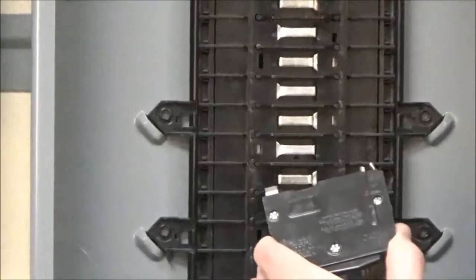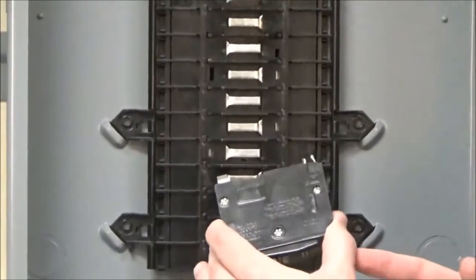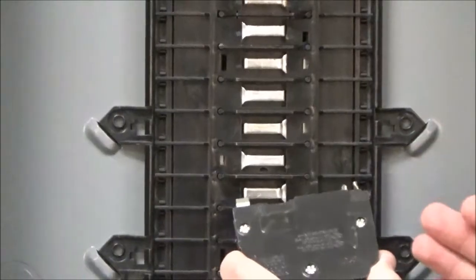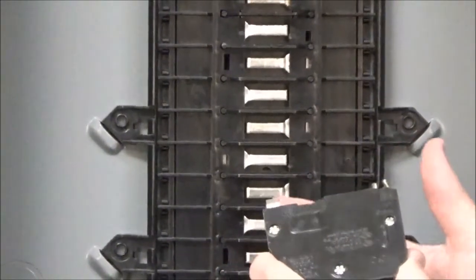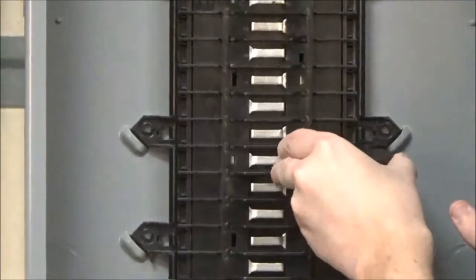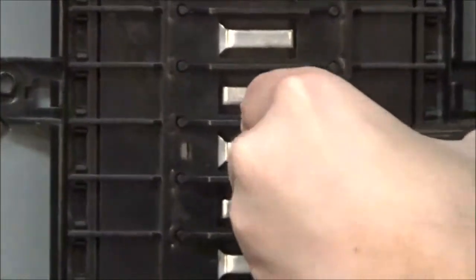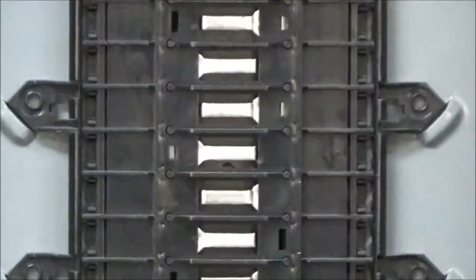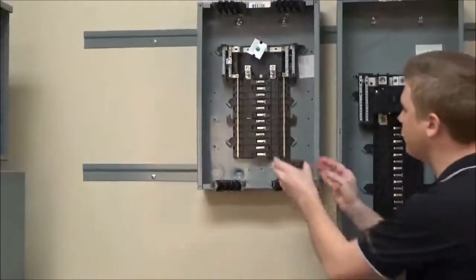To install them, you will first put the back rail clip onto the rail and then rock the breaker forward so that the bus clip can make the connection with the bus. It will install the exact same way on the plug-on neutral panel.